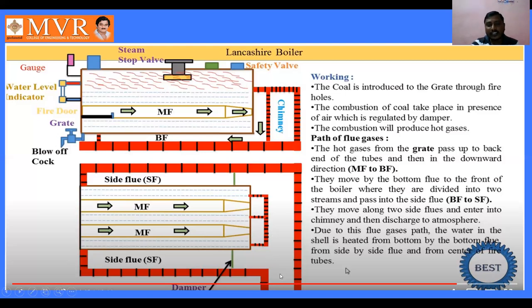After entering the two side flows, the gases enter the chimney and discharge to the atmosphere. Due to this flue gas path, the water in the shell is heated — from the bottom by the bottom flue, from the side by the side flue, and from the center of the fire tubes. When hot gases pass, through convection the heat is absorbed by the water, steam is generated at the top of the shell, and if superheated steam is required it passes into the superheater tubes.